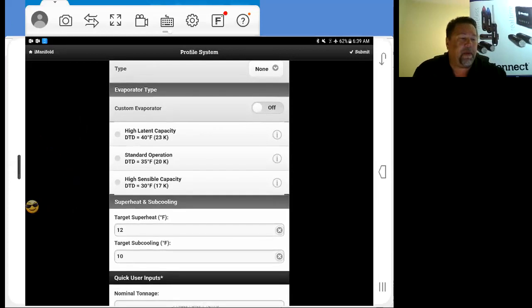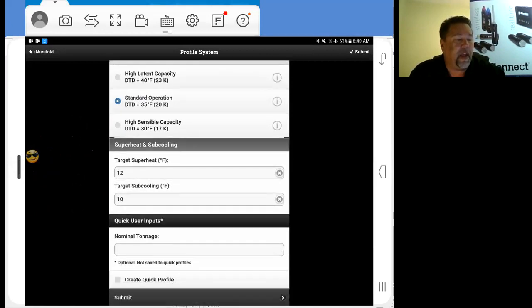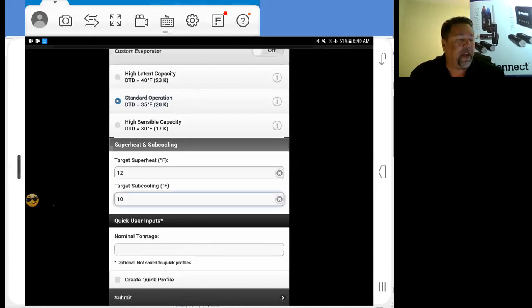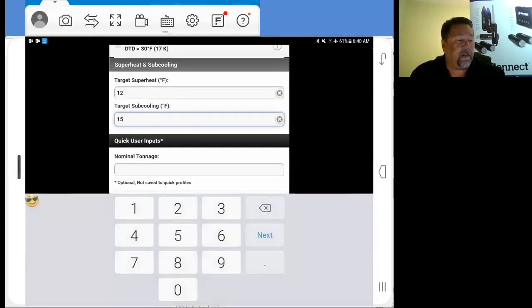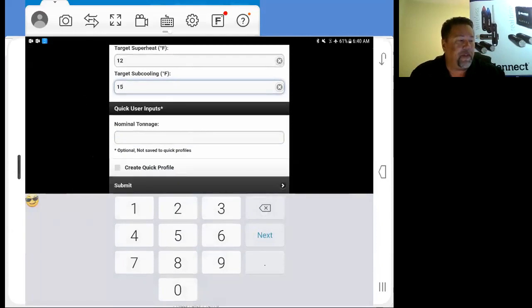Our evaporator type, custom evaporator, like I said, on custom applications. For HVAC and commercial and residential, we've got high latent, standard operation, high sensible. 90% of the time, you're going to just use standard operation. And our superheat and our subcooling targets, depending upon if it is a fixed orifice or a TXV, these numbers are changeable. This particular system we're going to look at right now has a subcooling target of 15. So we'll use 15. We'll create a quick profile.